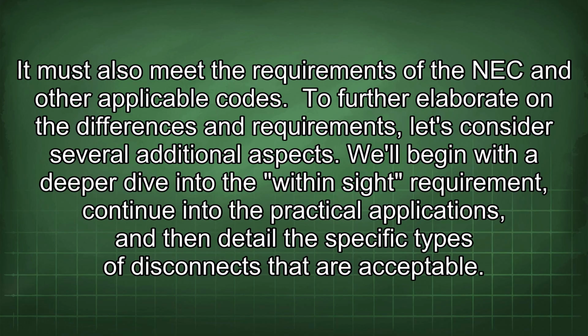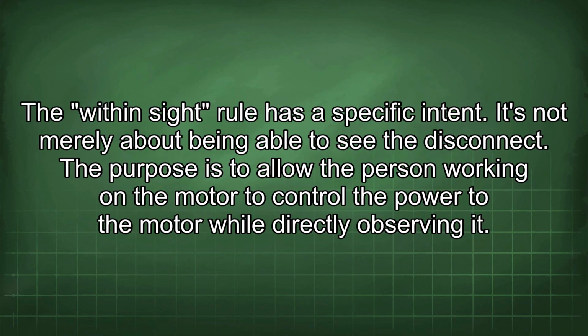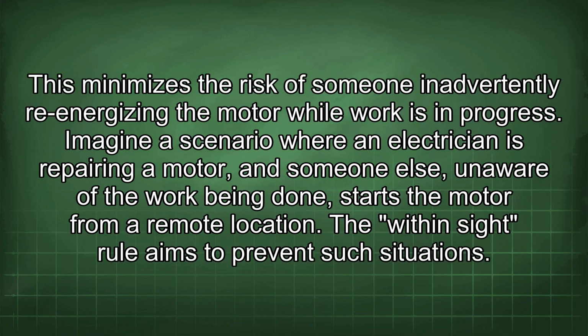To further elaborate on the differences and requirements, let's consider several additional aspects. We'll begin with a deeper dive into the within-sight requirement, continue into the practical applications, and then detail the specific types of disconnects that are acceptable. The within-sight rule has a specific intent. It's not merely about being able to see the disconnect. The purpose is to allow the person working on the motor to control the power to the motor while directly observing it. This minimizes the risk of someone inadvertently re-energizing the motor while work is in progress.